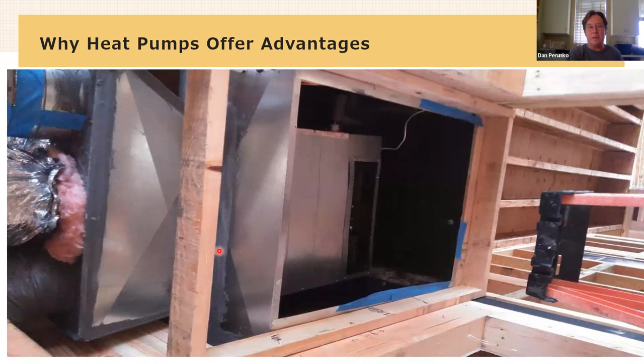The air handler butts up against the edge of this return plenum, and there's a supply plenum stuck off the side of that. So there are four ducts that come off the air handler, but the air handler itself is actually inside the return, so that the whole footprint of the system got shrunk. And this is done, I think, in both high and medium dollar jobs just to manage space. I think it's difficult and fussy to install, but if you did this a few times, you could get very good at it, and it makes for a super small footprint of system and allows you to squeeze it into a place in a building where you wouldn't normally have that option.